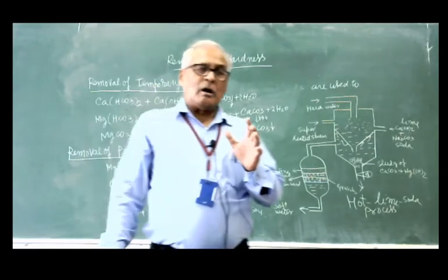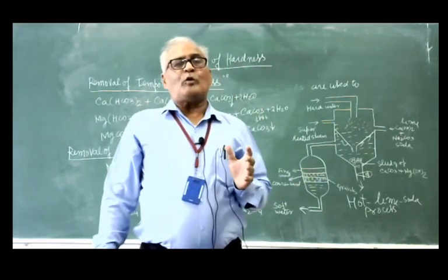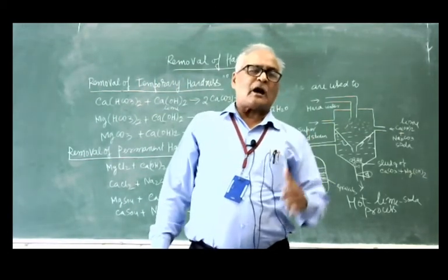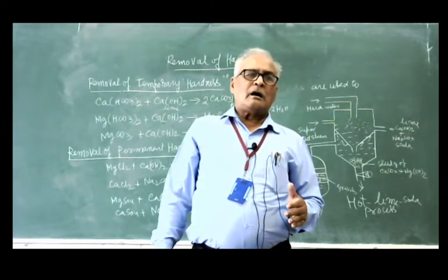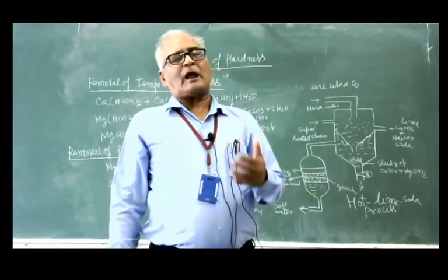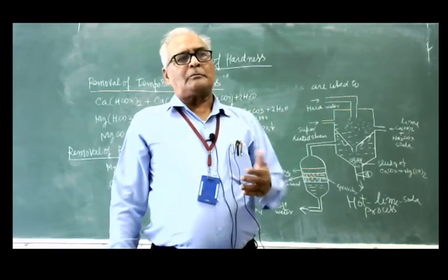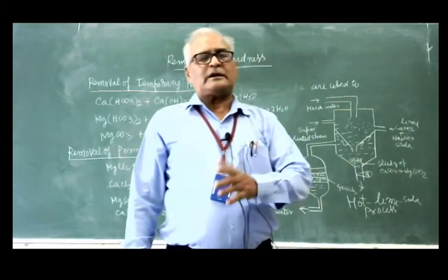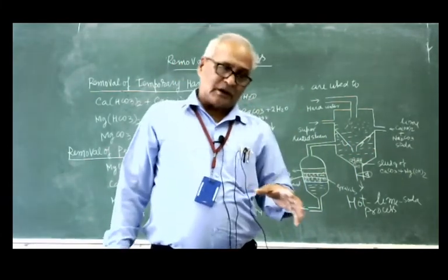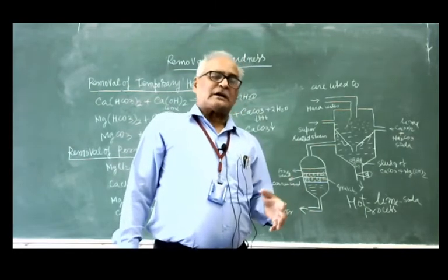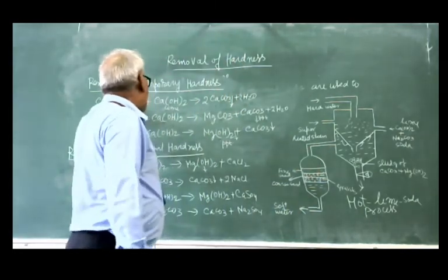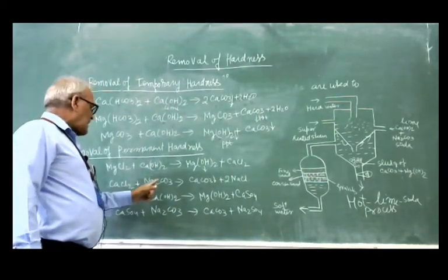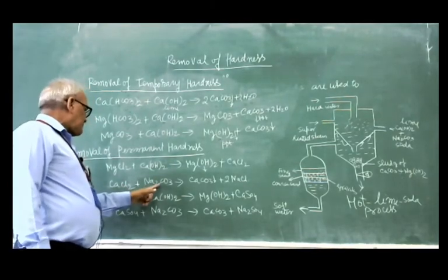So lime cannot remove permanent hardness created by calcium salts like calcium sulfate and calcium chloride, because lime does not react with them, therefore it is not required. But the bicarbonate of calcium can react with the lime. The calcium chloride does not react with the lime. It reacts with the soda.